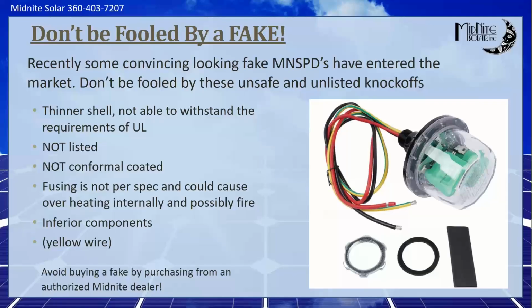So if you're using inferior plastics and the MOVs explode, then you're going to have molten stuff all over the house. The other reason is if you're in a scenario where the voltage goes slightly high. So let's say you've got an SPD 300 on your utility grid, and the grid goes to 600 volts for some reason. That SPD will conduct, and it will conduct a certain amount of power, and it'll get extremely hot. There's a fuse inside there on ours that opens and makes that safe before it actually catches on fire. It's a very edge case, but every surge arrestor has this edge case, and they all have a protection for that.